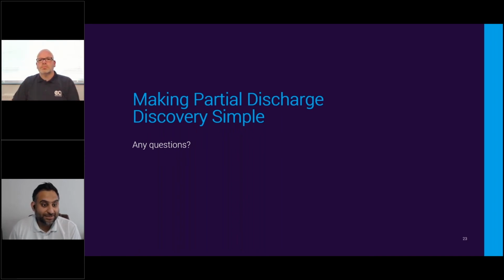What that means is the damage is severe enough that it could lead to a catastrophic failure, and you need to plan in an immediate remedial action. Typically, if things are bad enough and the activity is 30 dB or above, you need to be very careful when you are within the substation as well. DNOs or industrial customers normally put in restrictions on entry to the substations if they can't do any outages. But you might want to install some monitoring system there as well to make sure that any activity that you are picking up is not increasing, or to see how it's trending. So you can employ different methods in managing that partial discharge activity.